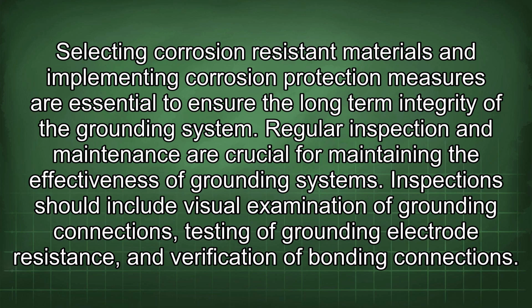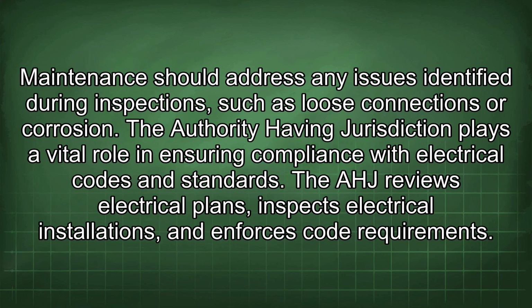Regular inspection and maintenance are crucial for maintaining the effectiveness of grounding systems. Inspections should include visual examination of grounding connections, testing of grounding electrode resistance, and verification of bonding connections. Maintenance should address any issues identified during inspections, such as loose connections or corrosion.